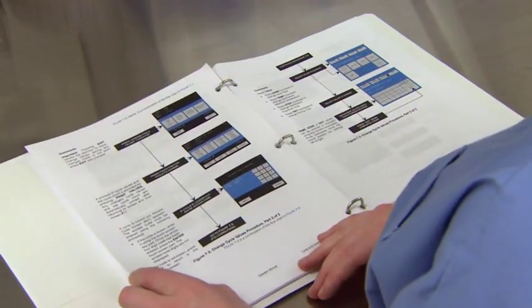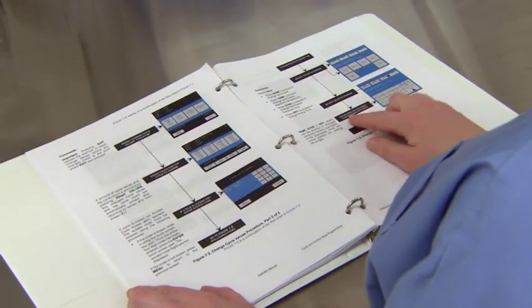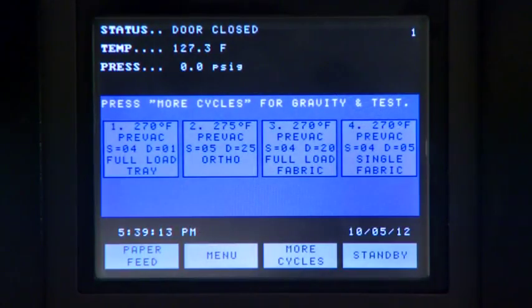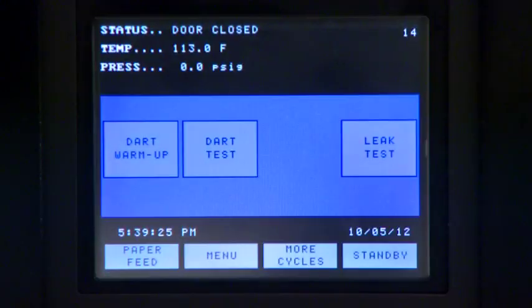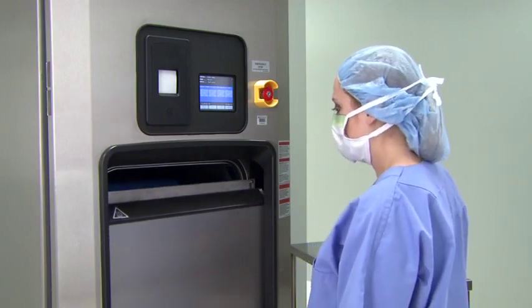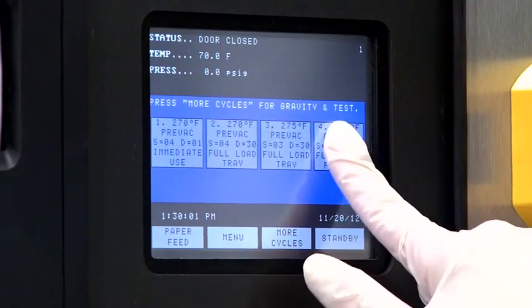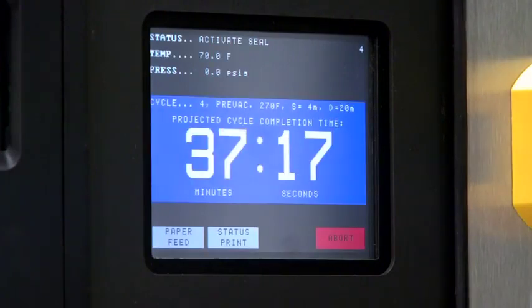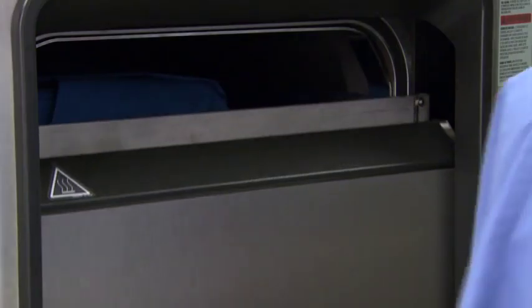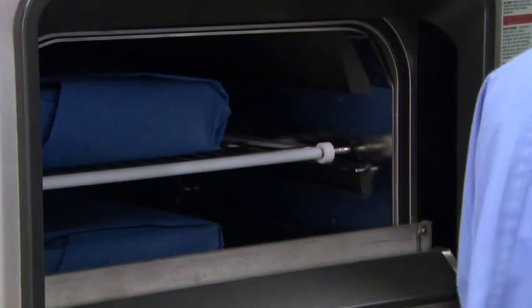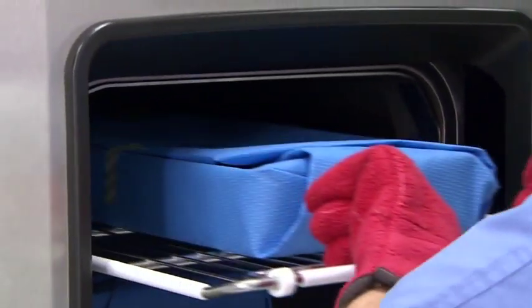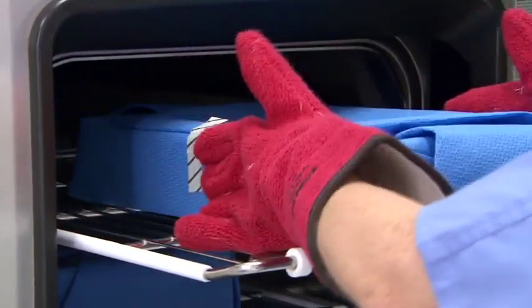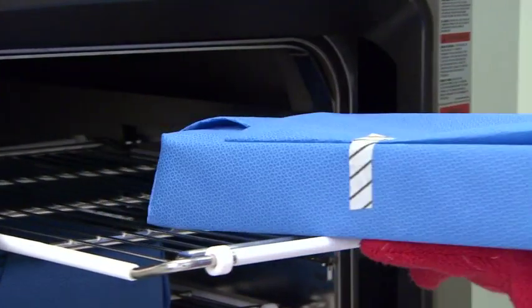Review the operator manual for the AMSCO 400 Series sterilizer for descriptions of the factory default cycle settings. Pre-programmed settings exist for several common load types, as well as leak and DART tests that are recommended to be run daily. The AMSCO 400 Series small sterilizer is programmed with one or more cycles intended to process items for immediate use. Immediate use is defined as the shortest possible amount of time between a sterilized item's removal from the sterilizer and its clean transfer to a sterile field.